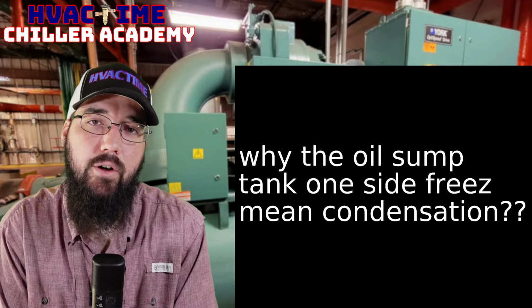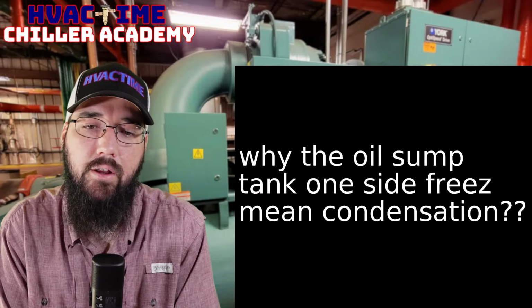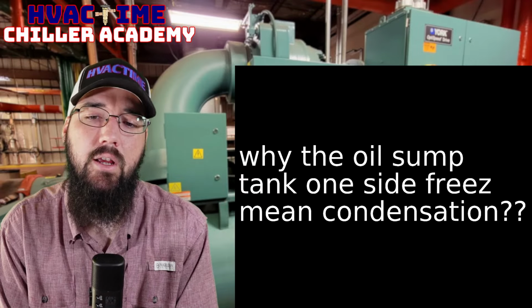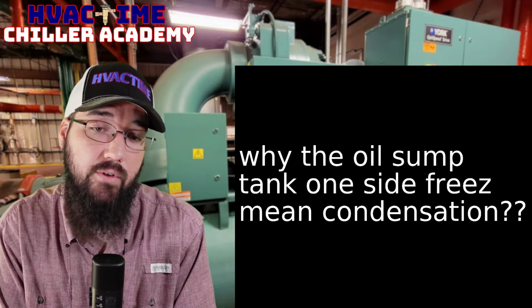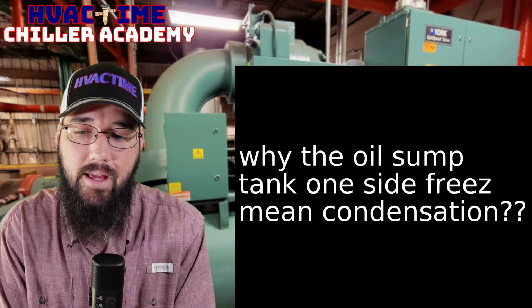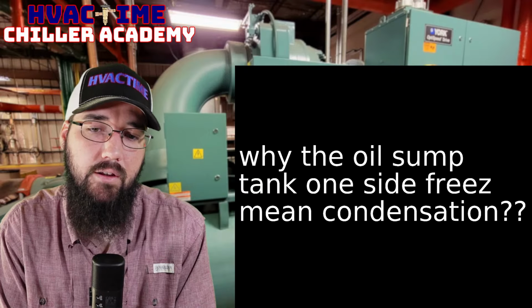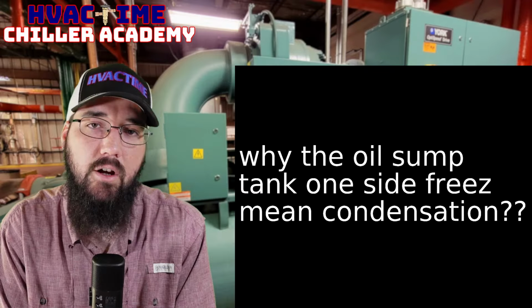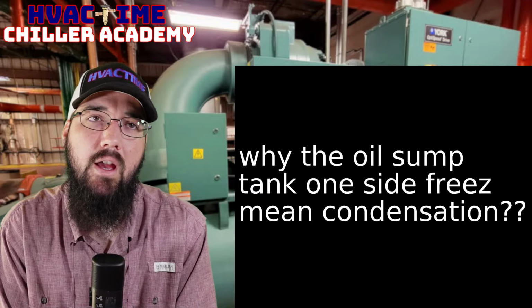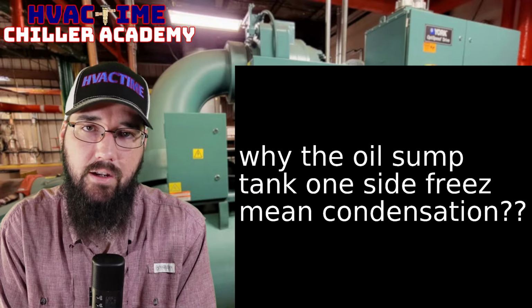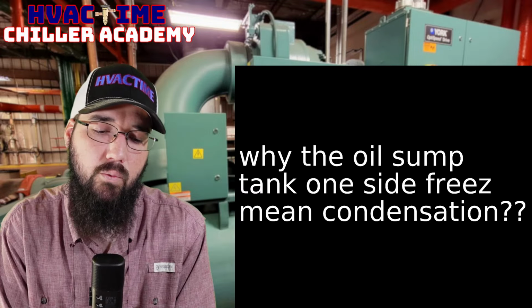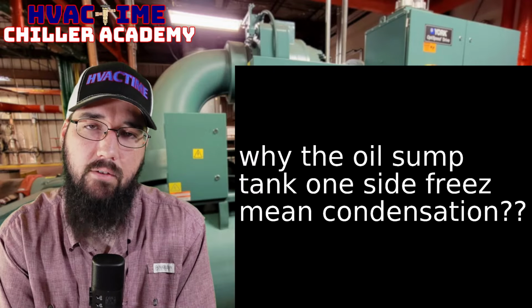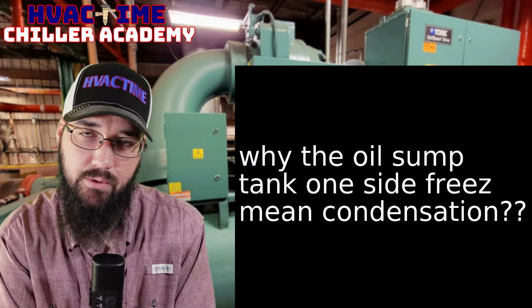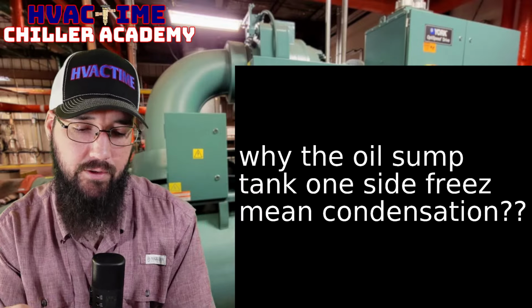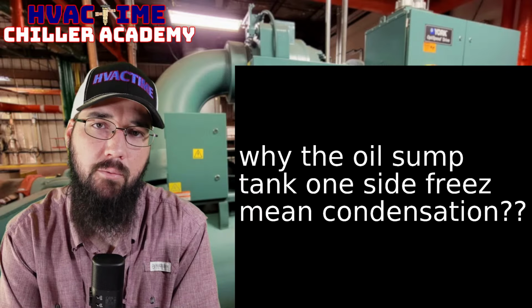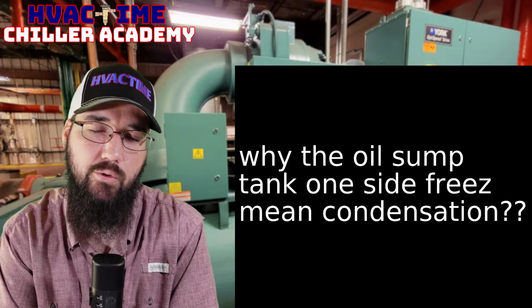So you'll see situations where you'll literally have the oil sump condensate or even potentially freezing. This is specifically going to be a centrifugal machine. And this comes back to the eductor return circuit, because keep in mind on these centrifugals, our oil system is in the low-pressure side of the system, so we also have our oil return circuits going straight into our oil sump assembly or oil tank, right? Depending on manufacturer definitions or terms they use, it's all the same thing. Sump, reservoir, tank, they're used interchangeably, just depends on who you're working on.